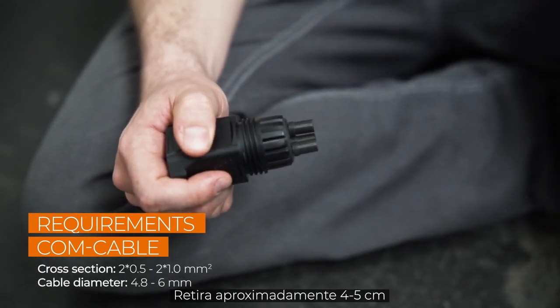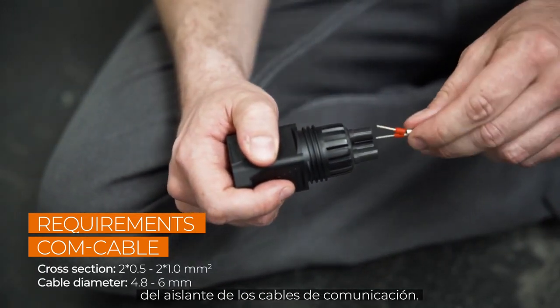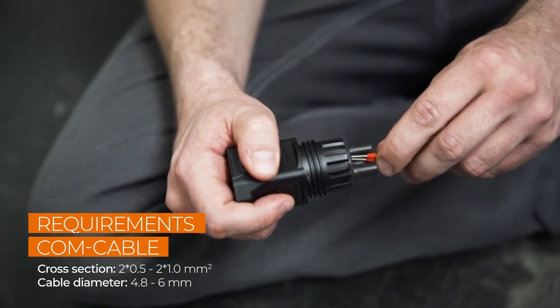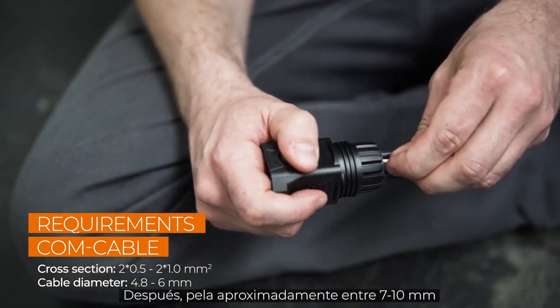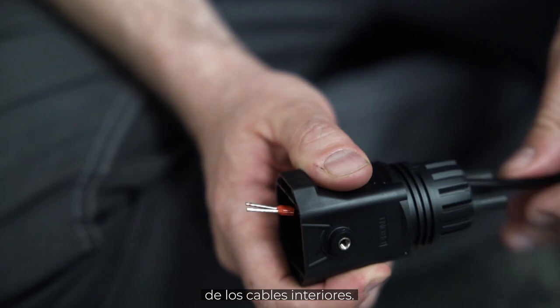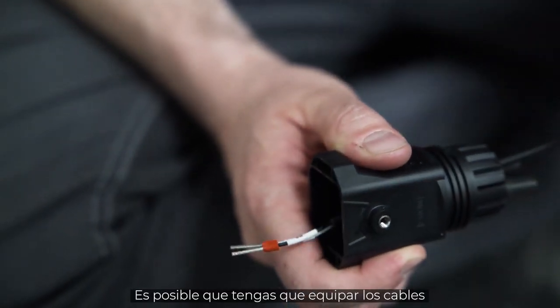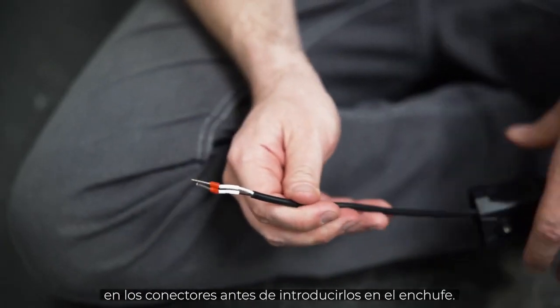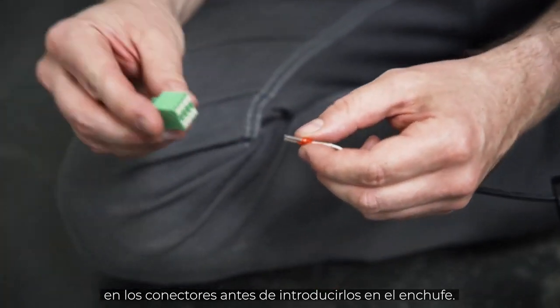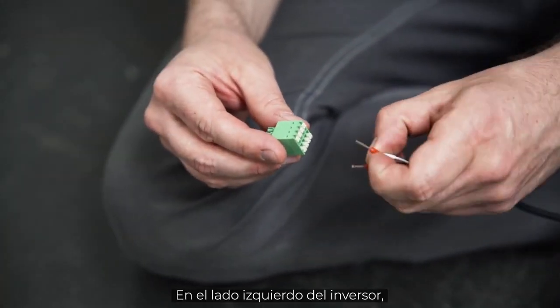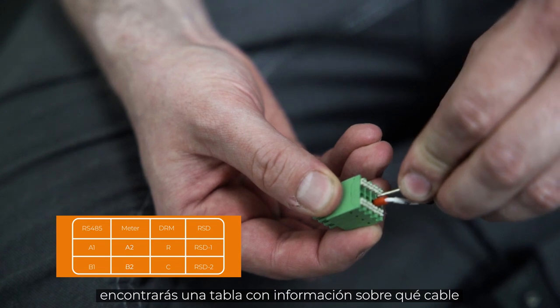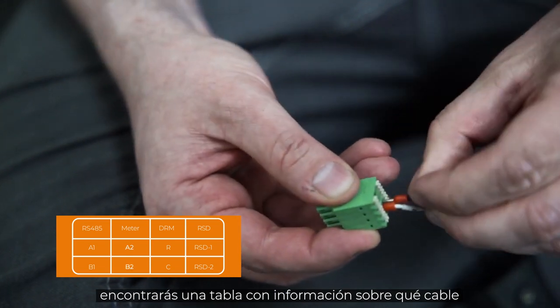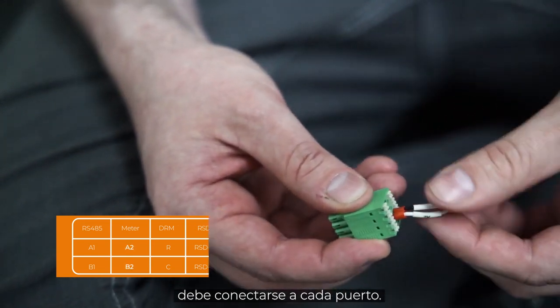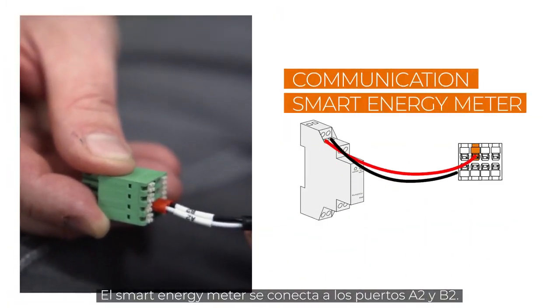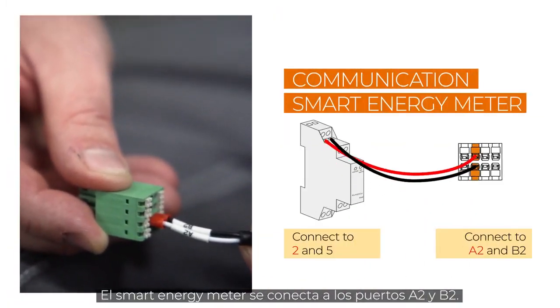Remove approximately 4 to 5 centimeters of the cable sheath of the communication cables. Then strip approximately 7 to 10 millimeters off the inner cables. If necessary, you may have to fit the cables with end sleeves before you push them into the plug. At the left side of the inverter, you will find a table with information about which cable has to be plugged into which port. The smart meter is connected to the ports A2 and B2.